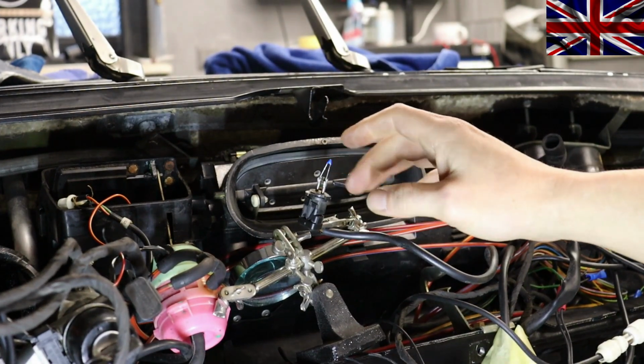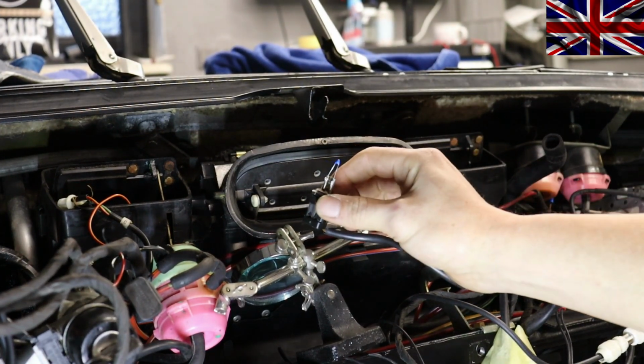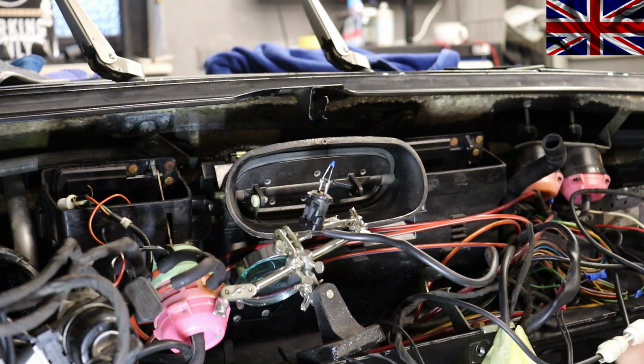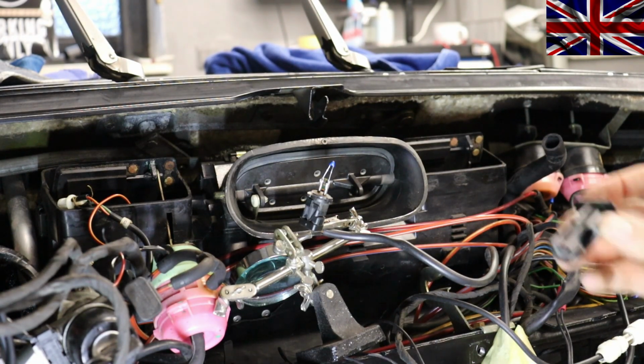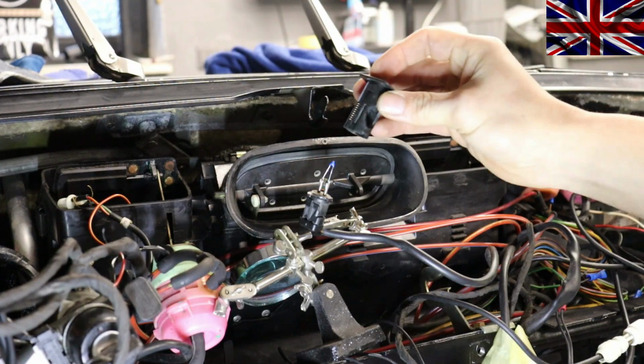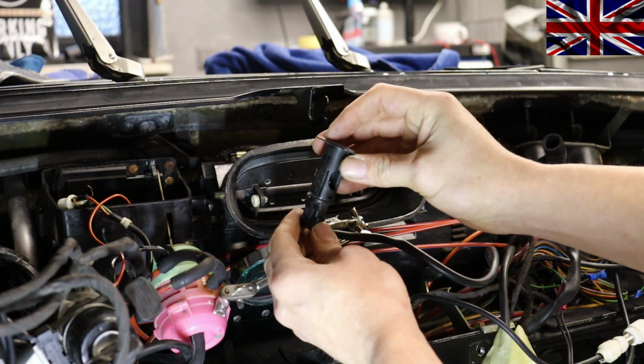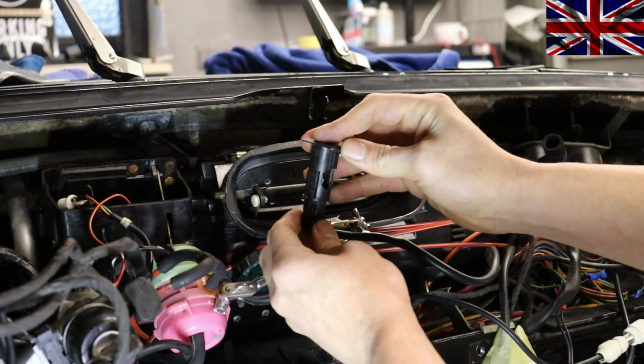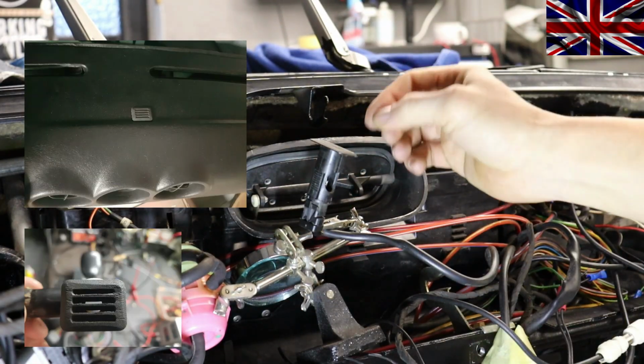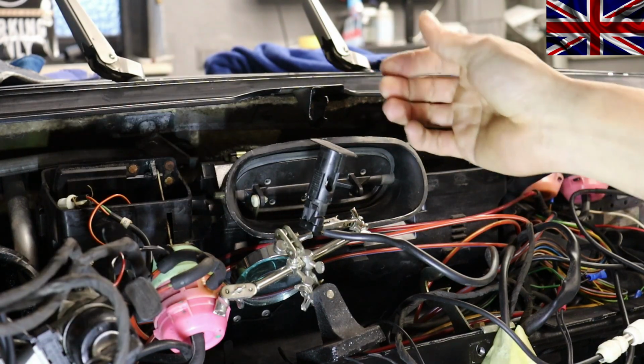This side branch here to the right hand side leads to this hose, which leads to the heat exchanger. Now we can get to the design flaw. Between the tube on the right hand side and the port side of the sensor, a rubber foam hose is mounted, which starts to get brittle and simply decomposes over time.